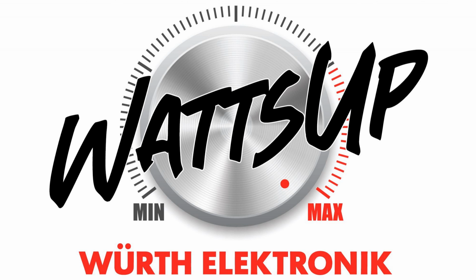radiated problems. Now again this shield needs to be connected to a quiet node. It can be usually on the primary side, because often the core is considered part of the primary. So this can be quite a good solution if you're having some radiated problems. But again, it comes with some drawbacks. Usually it's only good for radiated noise.